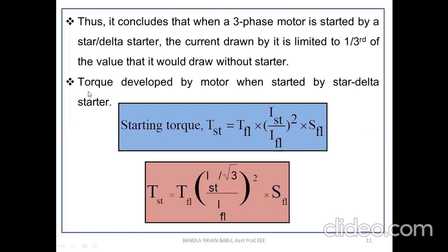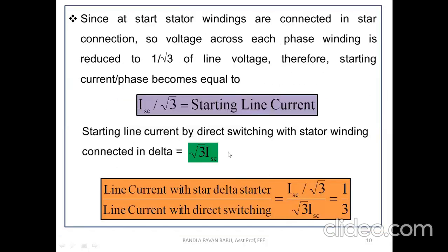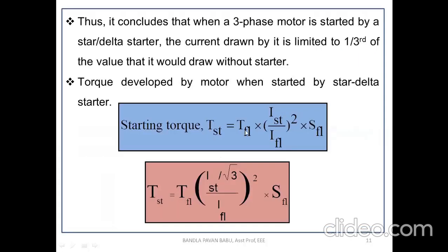Next, the torque developed by the motor when started by a star delta starter. It is the same approach: using these current equations, we substitute in the starting torque equation. We substitute the starting current here, that is IST by root 3. So how does it become?